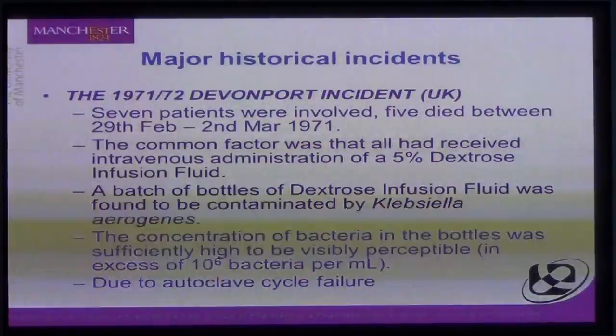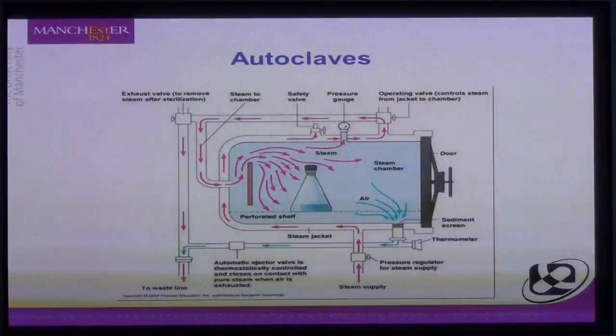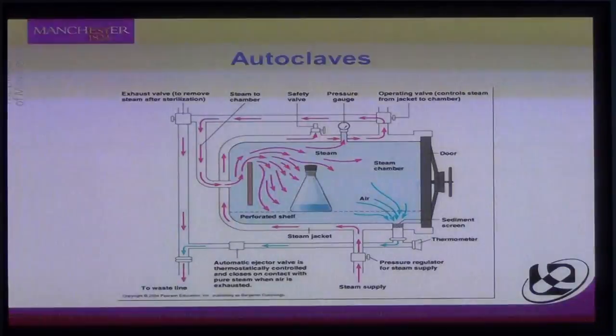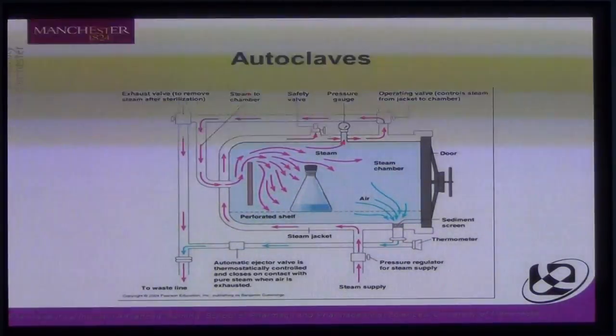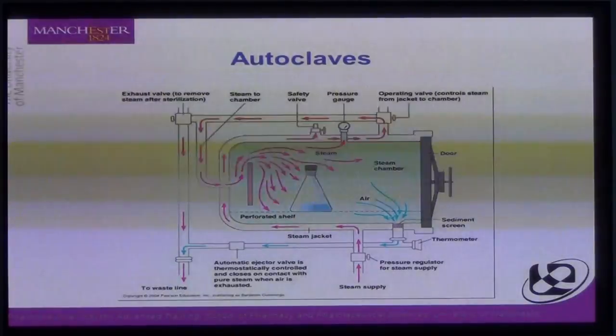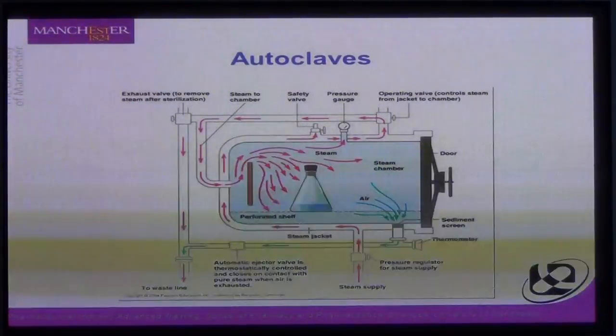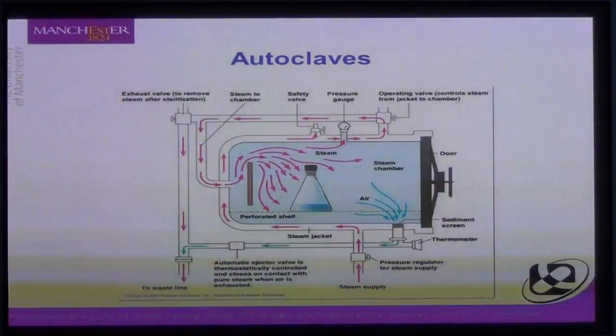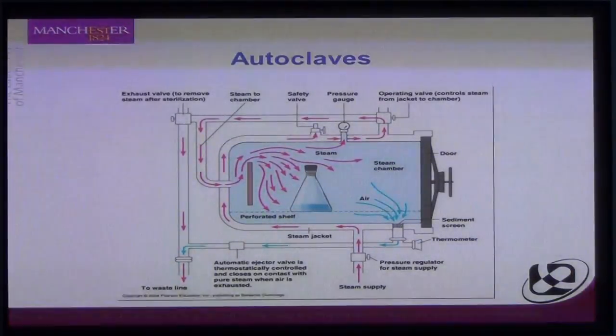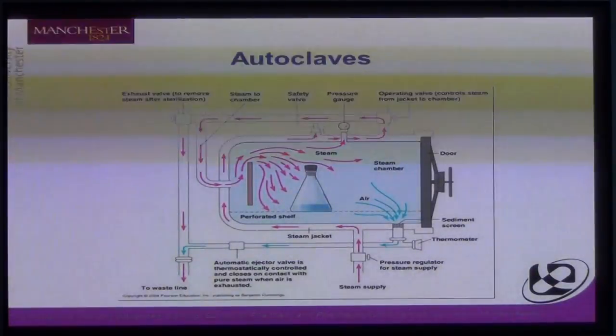This illustrates the key concept that before an autoclave is run, before it starts to heat up, all of the air must be removed by running a vacuum cycle. Where you get air pockets, the moist heat and steam don't penetrate, and it is possible that some items within the autoclave won't reach the right temperature, allowing microorganisms to survive. A diagram showing how an autoclave works is available in the course module — I strongly recommend reading that section.